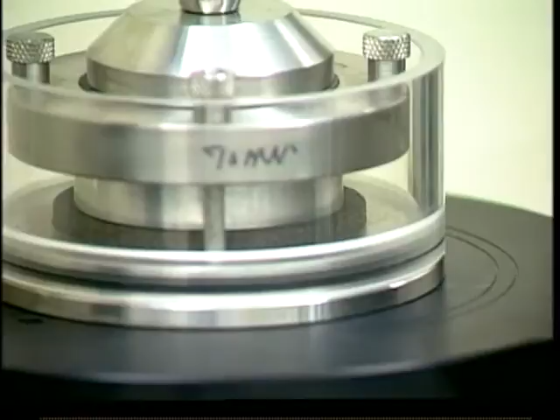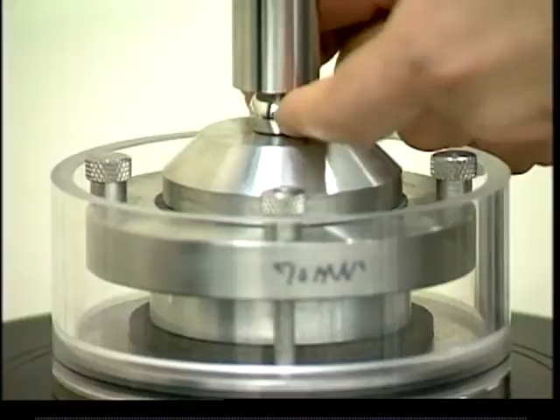Okay, what I just did here is put my consolidation cell in and center it. There are actually rings here. To give you an idea, the rings are the typical sizes of soil samples: 1.4, 2 inch, 2.5, 2.8, and 4 inch. So you center it here, and get as close as possible to the load cell button, so you know that this is moving here. And everything is good to go here.